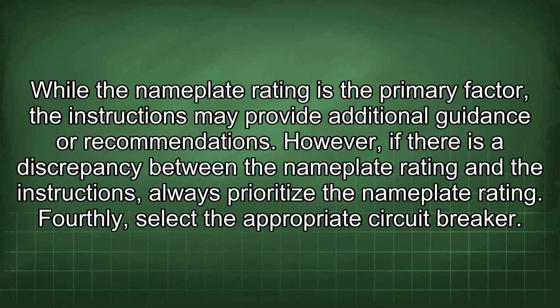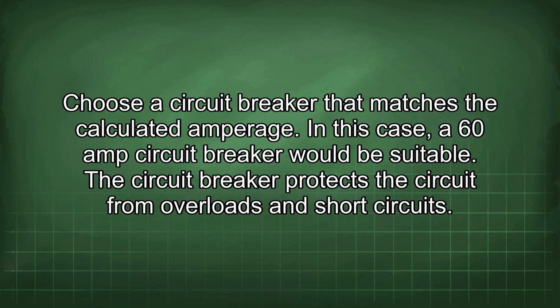However, if there is a discrepancy between the nameplate rating and the instructions, always prioritize the nameplate rating. Fourthly, select the appropriate circuit breaker. Choose a circuit breaker that matches the calculated amperage. In this case, a 60 amp circuit breaker would be suitable. The circuit breaker protects the circuit from overloads and short circuits.